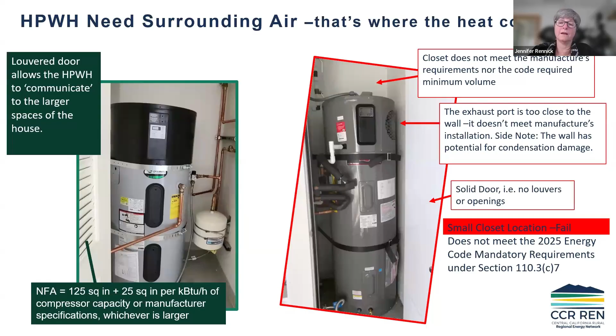And then, unfortunately, what we're seeing—which is the reason for all these mandatory measures—is that a lot of times these heat pump water heaters are being shoehorned into really tight closets with solid doors. So it's not meeting the manufacturer's recommended or code-required minimum volume around the space. With a solid door instead of louvered openings, it can't communicate with the larger space. Also, the exhaust port is sometimes pushed right up against a wall, and there's potential damage that could happen there.